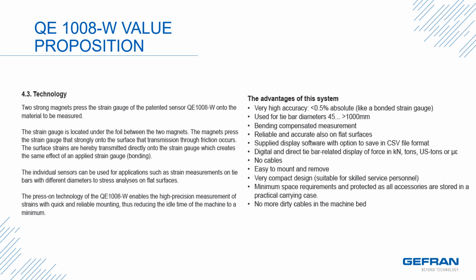There's no cables, big plus. Again, no need to take the doors off the machine itself. That could have taken you up to over an hour in terms of the calibration. With this wireless technology, it will give you the advantage to cut that calibration time in more than half. You could probably do it within a 20-minute window, and it will give you all the data that you need. It's a very compact design. We give you the case along with it. It's very portable. The software itself, there's no license required, so you can have the software on multiple laptops out on the floor. So these are all advantages that we see for the Gefran Sensormate tie bar calibration system.